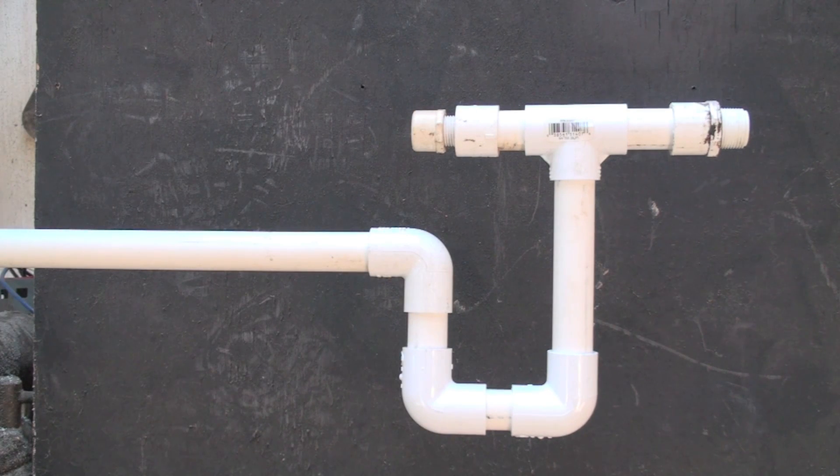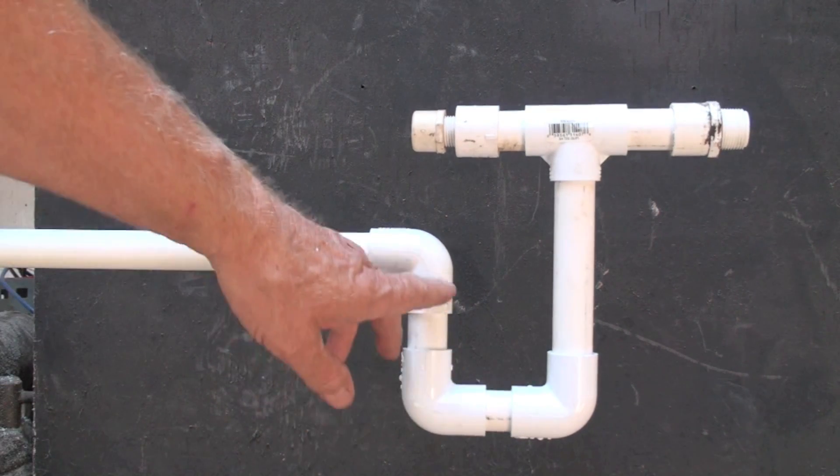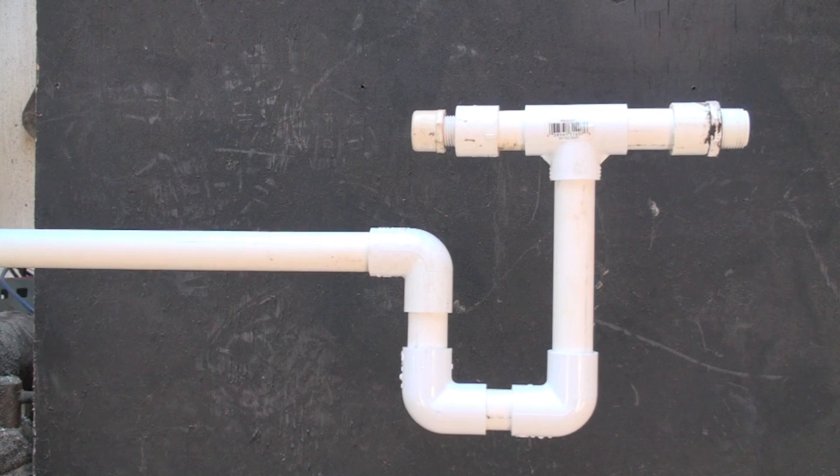That's a P-trap on the air conditioner evaporator. Pretty simple. I want at least two inches of water in this trap. And you can see there I've got more, but that's fine.